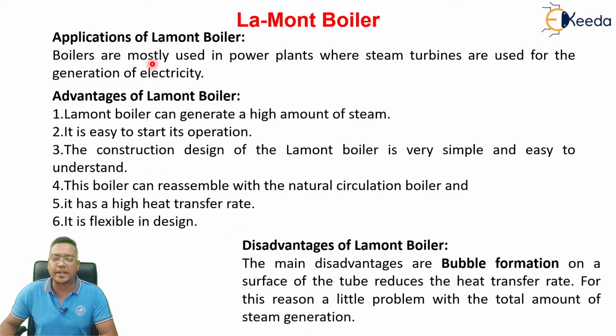Lamont boiler application: it is used in the power plant for the generation of power. Advantages of the Lamont boiler are: it can generate a high amount of steam. It is easy to start its operation. The construction design of the Lamont boiler is very simple and easy to understand. This boiler can resemble the natural circulation boiler and it has a high heat transfer rate. It is flexible in design.